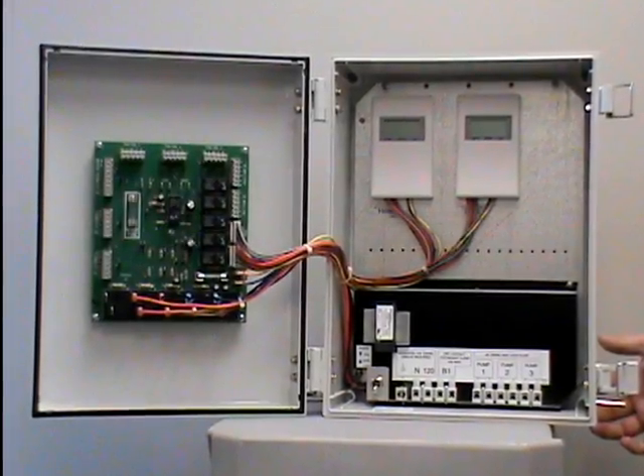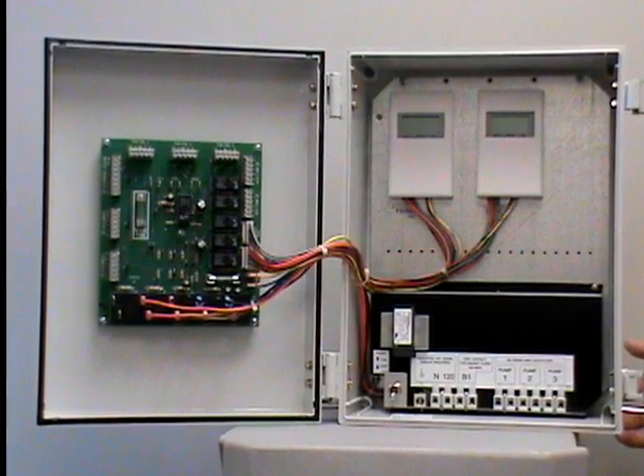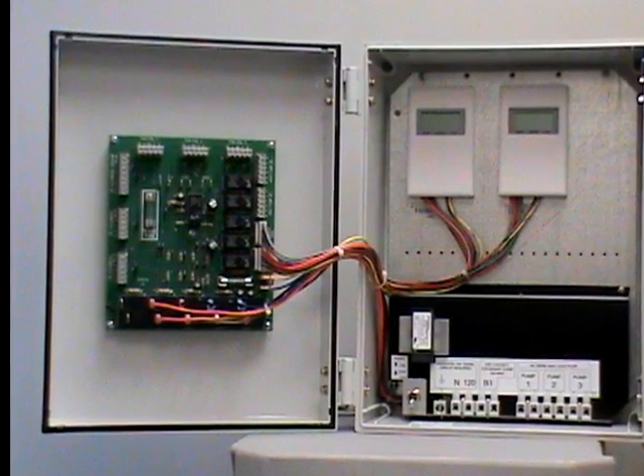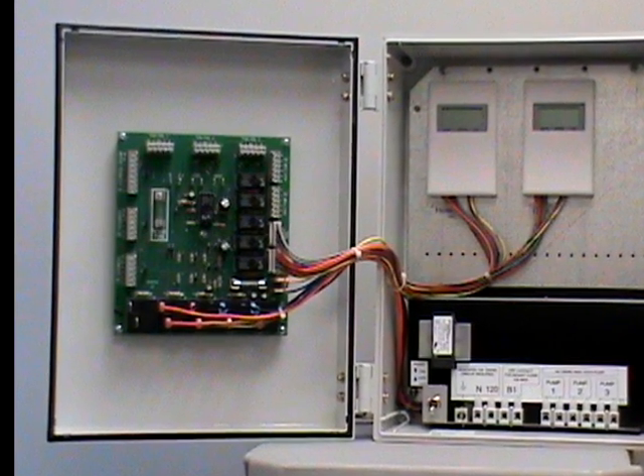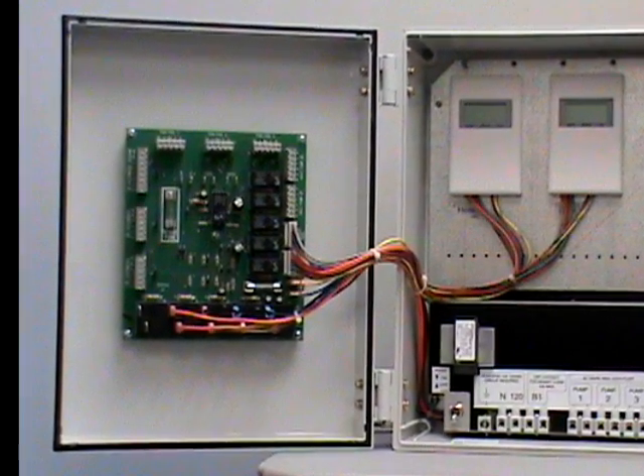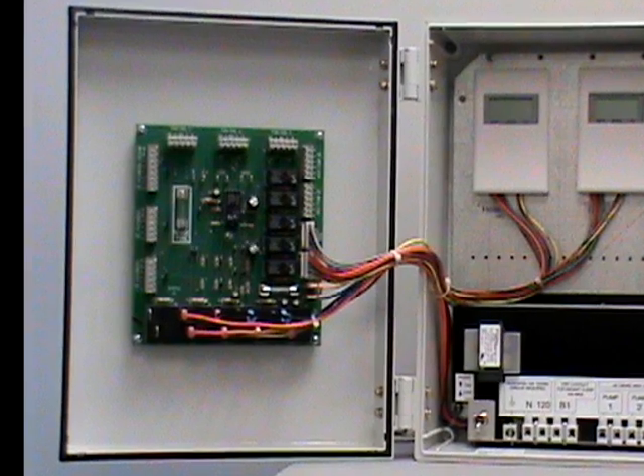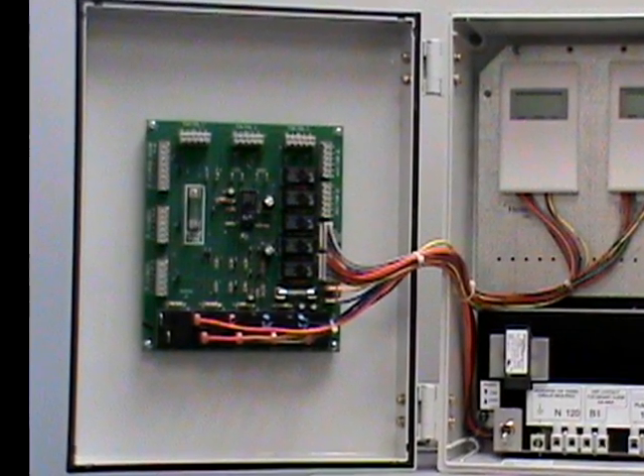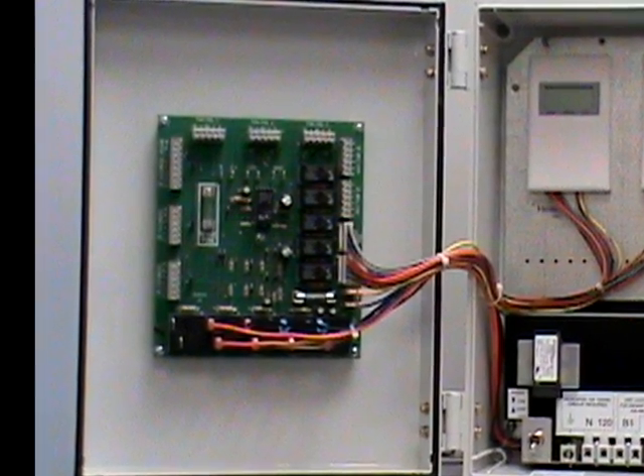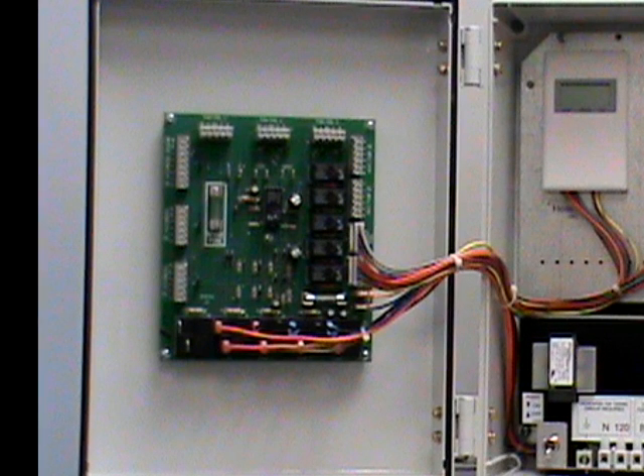Inside the door of the control module is a printed circuit board which provides a location to land all of the low voltage wiring from each of your system components in one location. The circuit board is protected by a standard 2-amp bus type fuse and even comes with a spare. A key feature of the Terra-Therm hydronic control module is the ability to isolate low voltage for all the hydronic system components, including the heat pumps and fan coils or furnaces. In other words, multiple components, each with their own transformer, can be connected to the hydronic control module but remain electrically isolated from each other.